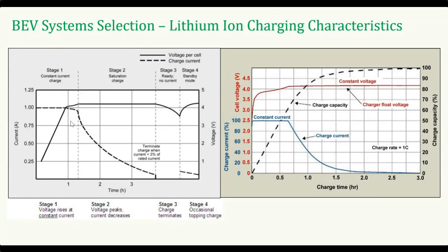In this figure, stage 1 is the constant current charging, where the battery reaches peak voltage quicker with constant charging. Stage 2 is the saturation charge, which takes longer, and full charge is reached when current decreases to 3 to 5% of the cell's amperage-hour rating.